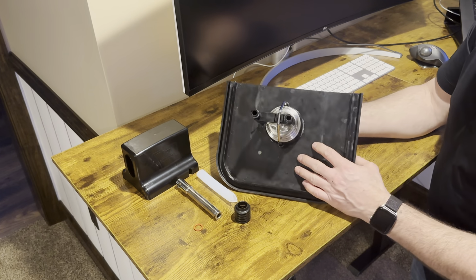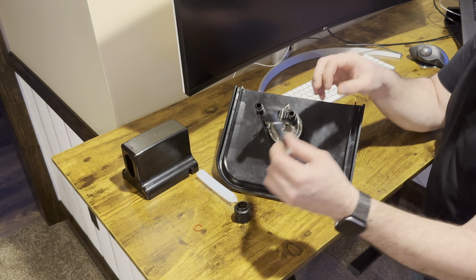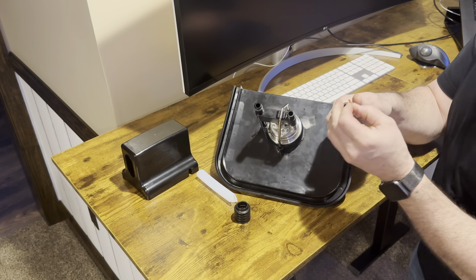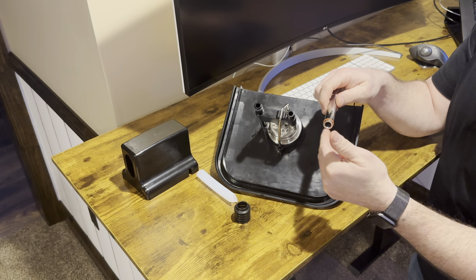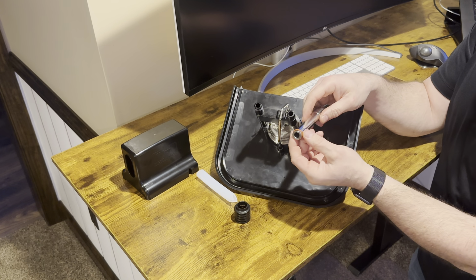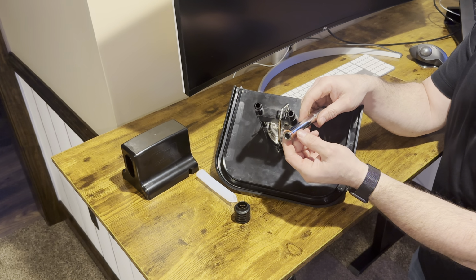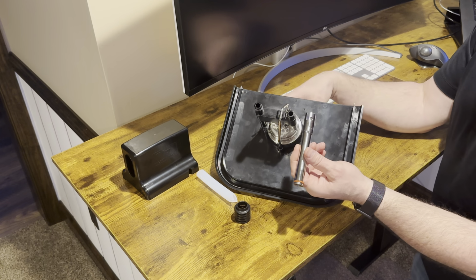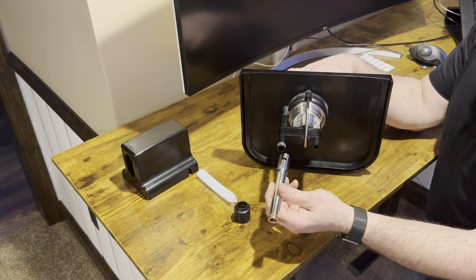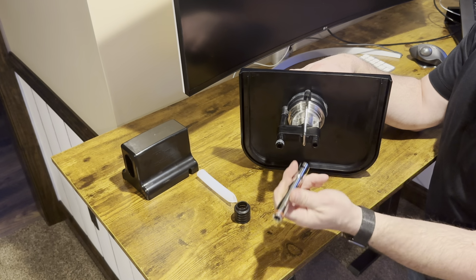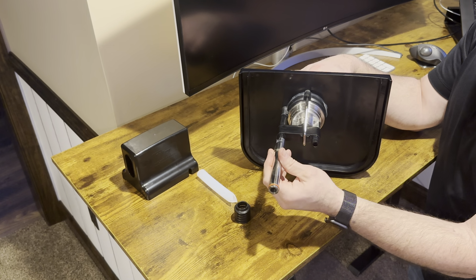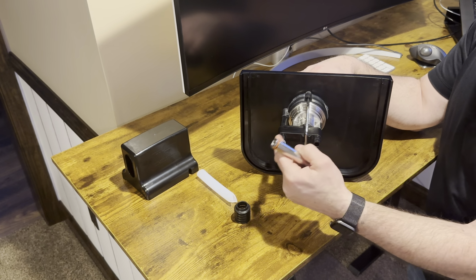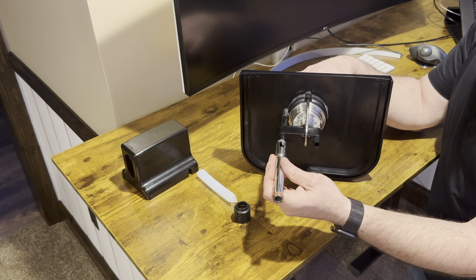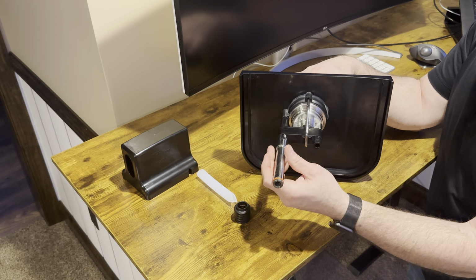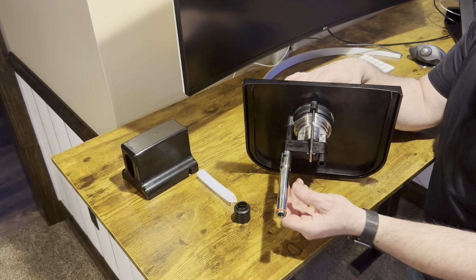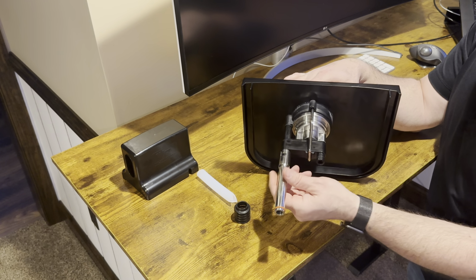And then take your feed tube, and you have an O-ring on the end of that. Snap that guy on. A little bit of lubricant on here when you're ready to go into the machine also helps that fit in there better. And this, align these stubs to the notch in the tube, and a little bit of lubricant on these O-rings as well helps keep them from catching when that tube goes up on there. And then turn that just 1/8 of a turn, and it latches in that notch.